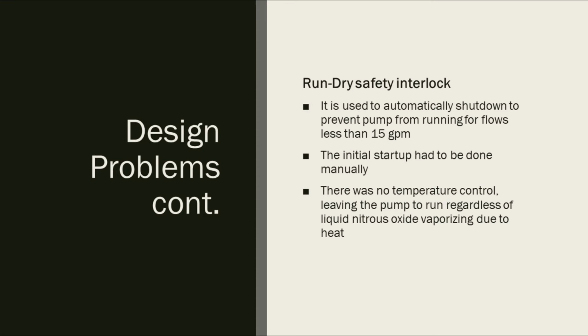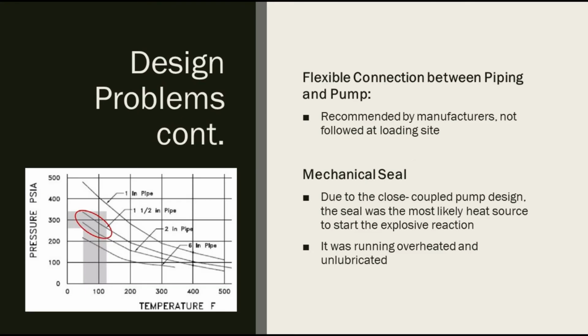Run-dry safety interlocks are used to automatically shut down to prevent a pump from running low. This one specifically was set for flows less than 15 GPM. What it meant was that during the initial startup, an operator had to manually make sure that the liquid levels reach 15 GPM and then allow the safety interlock to take over. There were no temperature controls, leaving the pump to run regardless of liquid nitrous oxide vaporizing due to heat, causing the pump to run dry eventually, ultimately leading to a decomposition reaction.